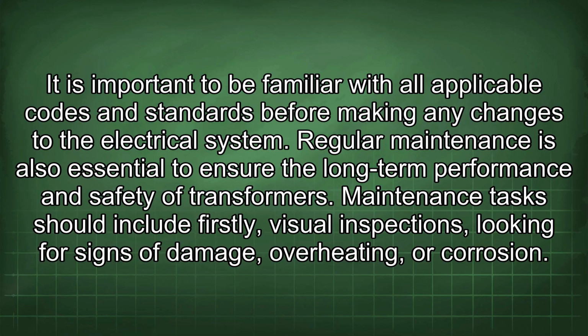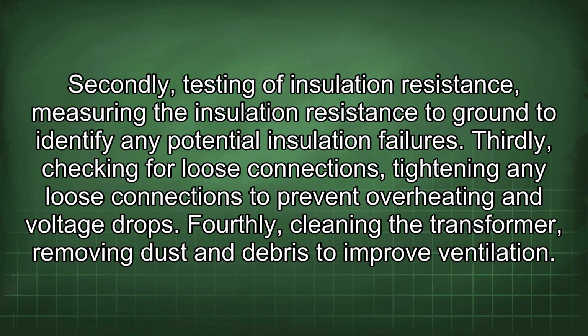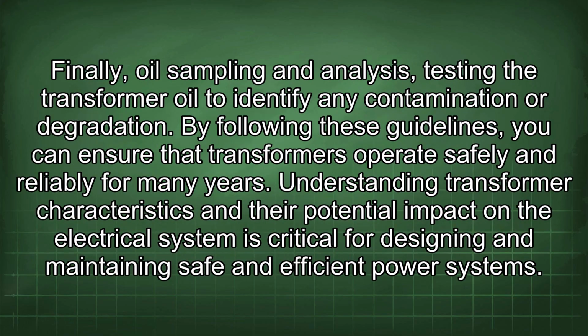Regular maintenance is also essential to ensure the long-term performance and safety of transformers. Maintenance tasks should include, firstly, visual inspections, looking for signs of damage, overheating, or corrosion. Secondly, testing of insulation resistance, measuring the insulation resistance to ground to identify any potential insulation failures. Thirdly, checking for loose connections, tightening any loose connections to prevent overheating and voltage drops. Fourthly, cleaning the transformer, removing dust and debris to improve ventilation. Finally, oil sampling and analysis, testing the transformer oil to identify any contamination or degradation. By following these guidelines, you can ensure that transformers operate safely and reliably for many years.